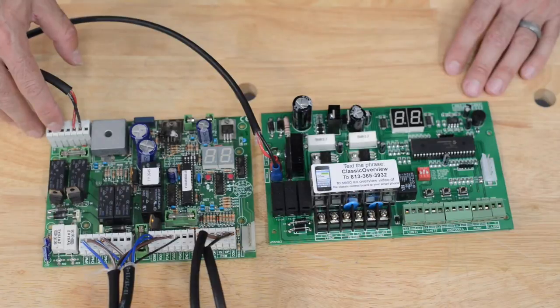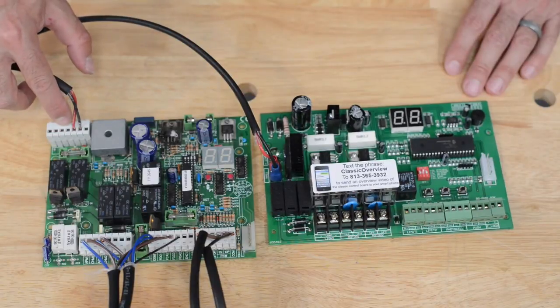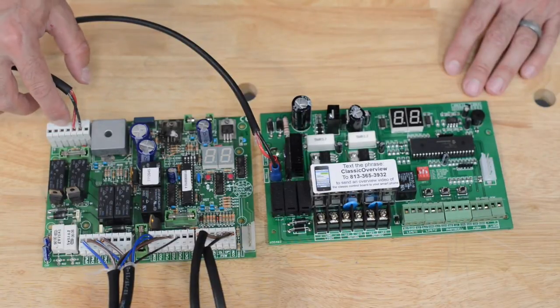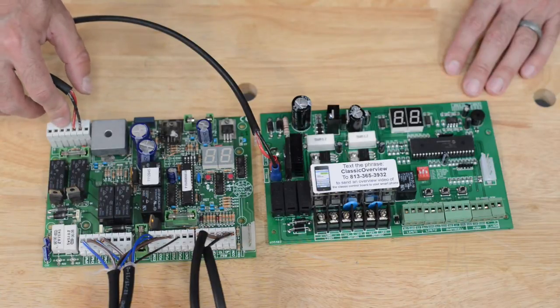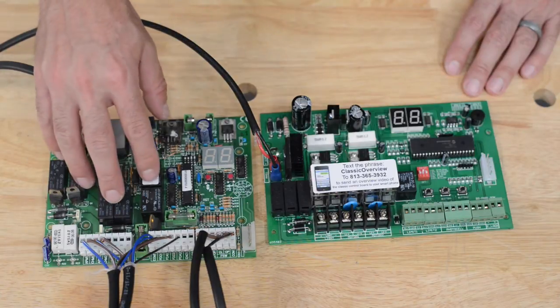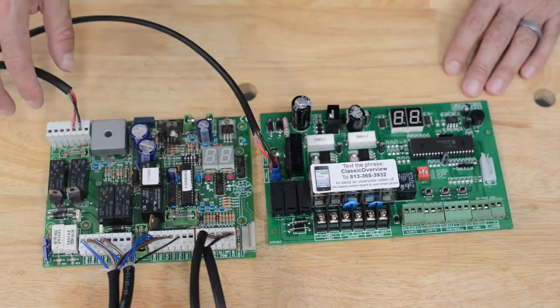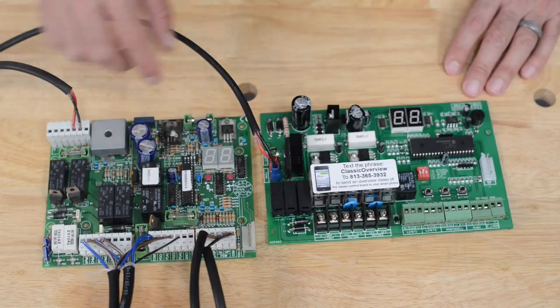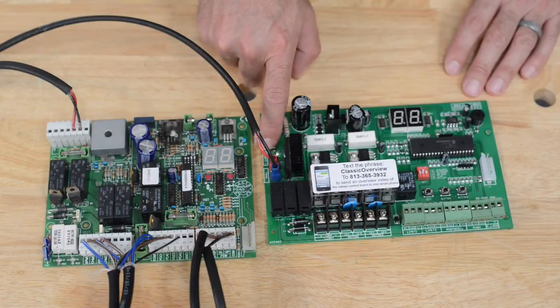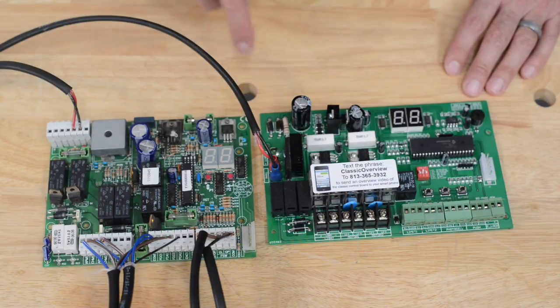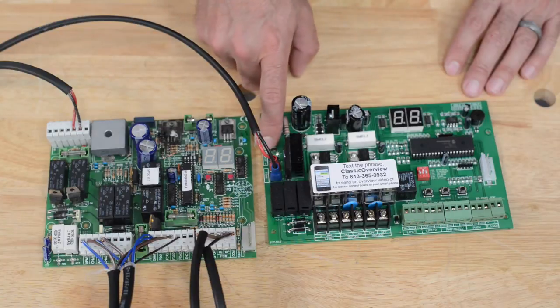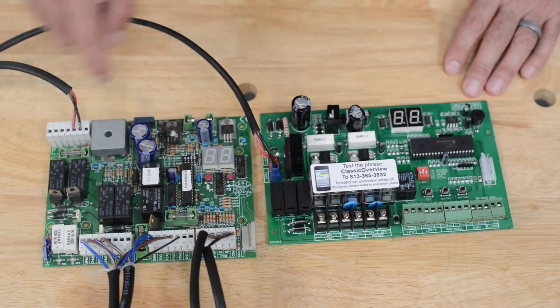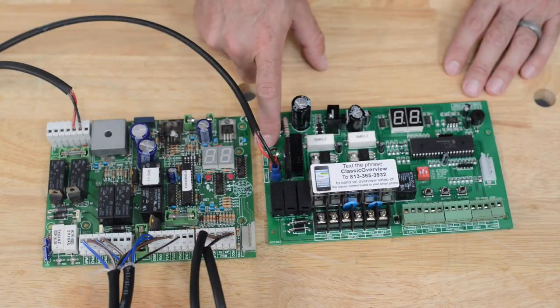On our old board here, we don't have anything in these second two sets of terminals. This is your battery positive and negative. If we did have a backup battery, which is not required for either of these control boards, the backup battery would go where you see BAT positive and negative. On the BAT positive and negative, just like on this board, you do have to respect polarity.